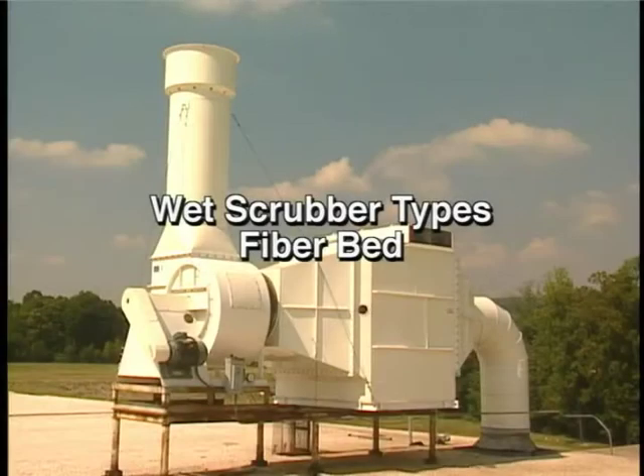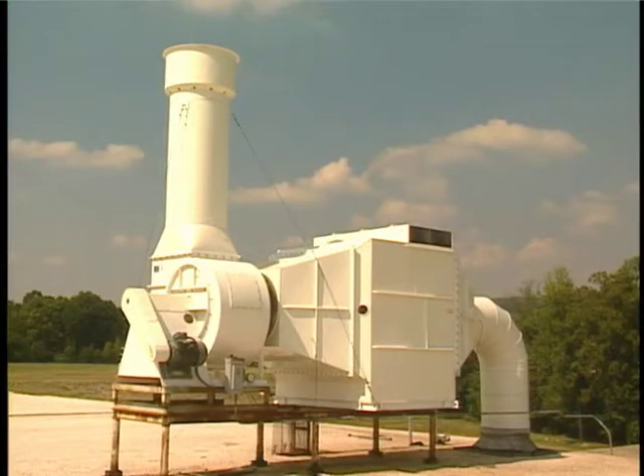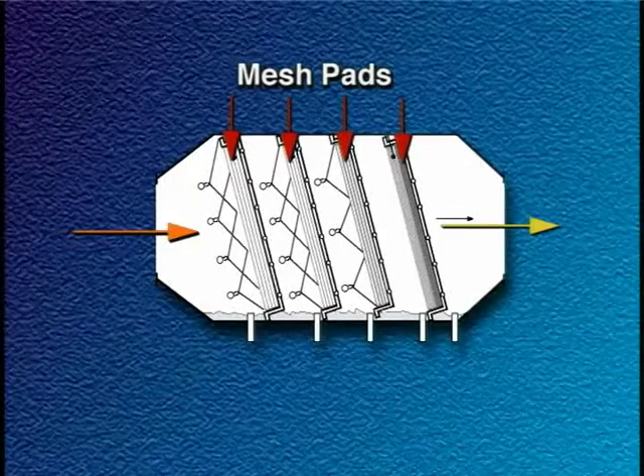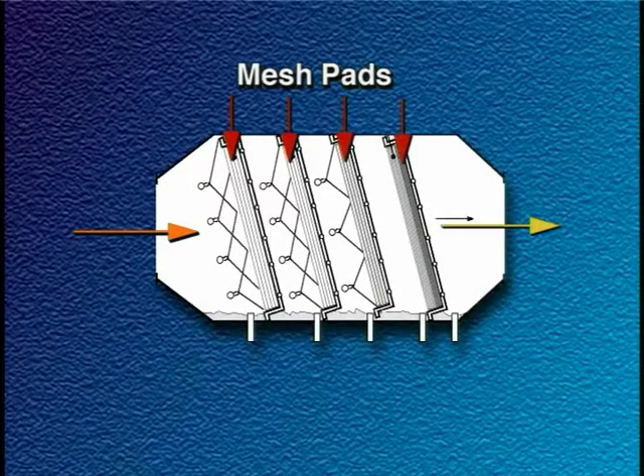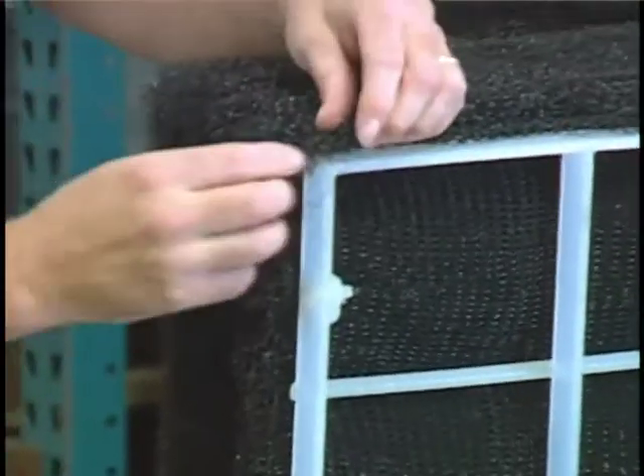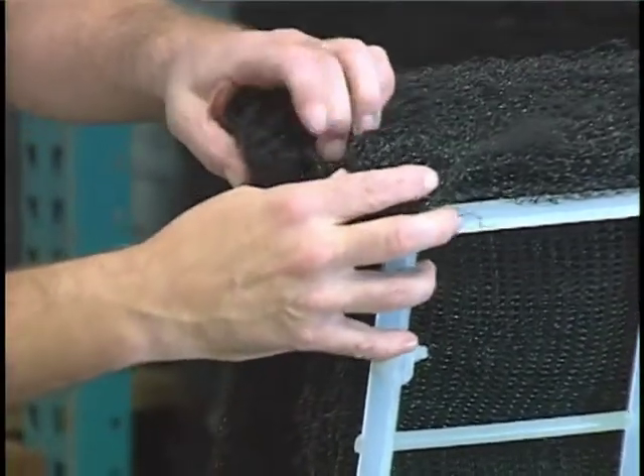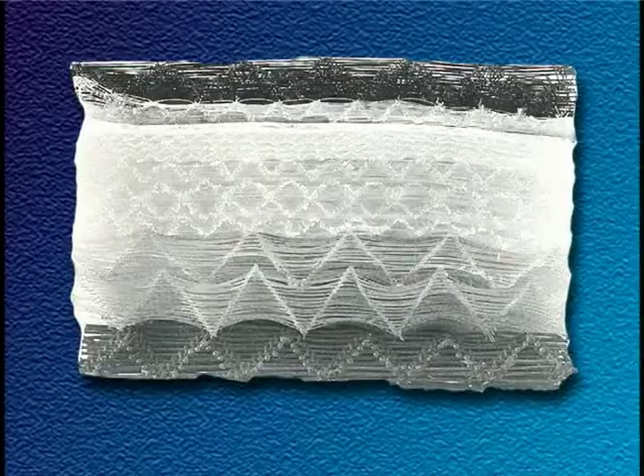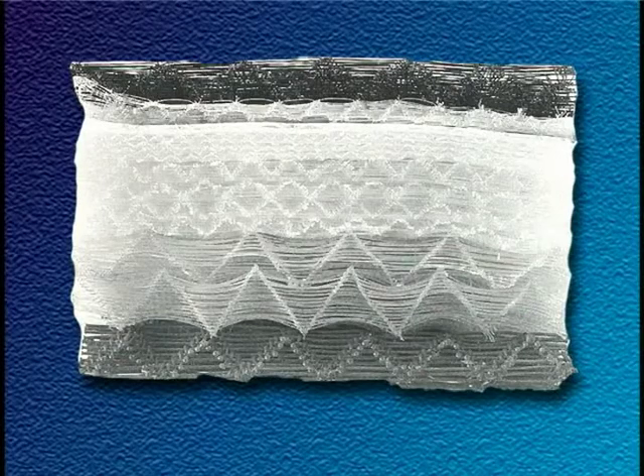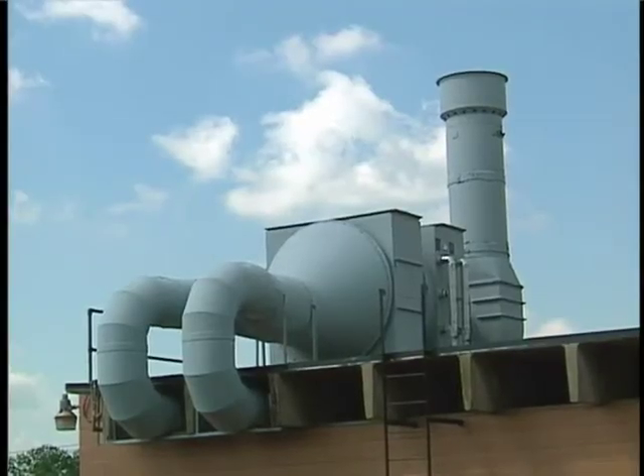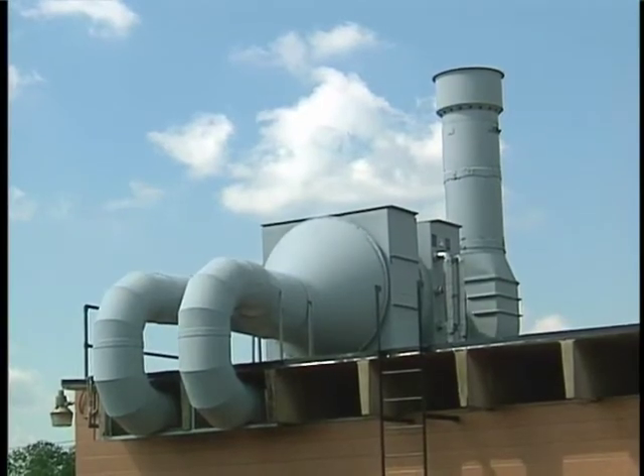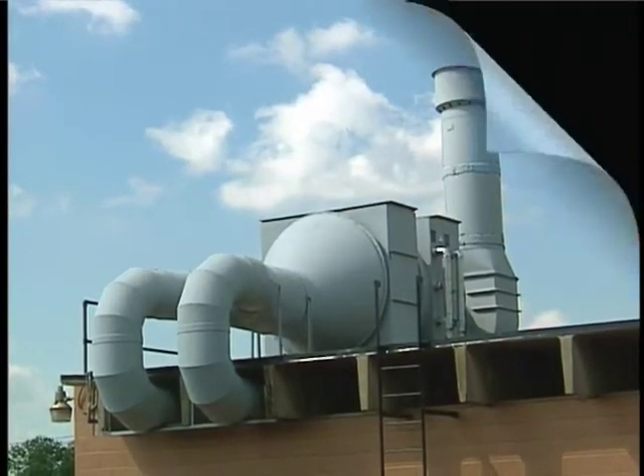A medium energy device used for the collection of liquid particles is the fiber bed scrubber. In this collector, the contaminated gas stream flows horizontally through one or more vertical mesh pads composed of randomly interlaced fibers or woven fibers. The density of the fibers controls the size of droplets that are removed. Scrubbing liquid is sprayed continuously or intermittently on the inlet side of each pad.